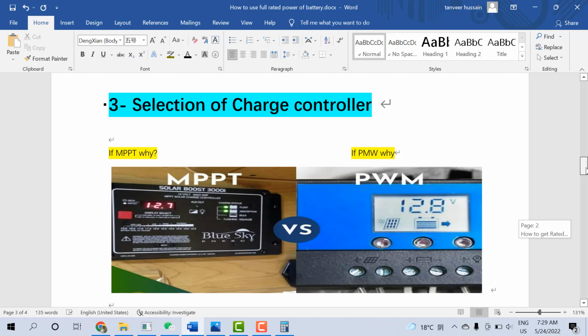The reason one: if the distance between the solar panel and your inverter or battery is long, then you have to use MPPT. And if you don't have a good enough cable, and you are using a lot of high power, a lot of solar panels - for example 1000 watt, 2000, 3000 watt - then you have to use MPPT. So if the wire distance between the inverter and the solar charge controller is less, then you can use PWM. You can use MPPT, but MPPT is expensive. If you use PWM in that case, you will get the same performance.